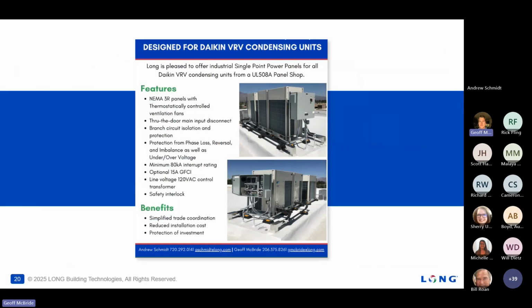Single point power, as I'm out of time, is something we can also do. It's about an hour-long presentation. It's essentially when you have either single or double module condensing units and you wish to combine the power into a single feed and add phase protection. And we can get into why that's important in our market, or really in the United States. These air-cooled heat pumps are all filled with electronics, and they really need to be protected.